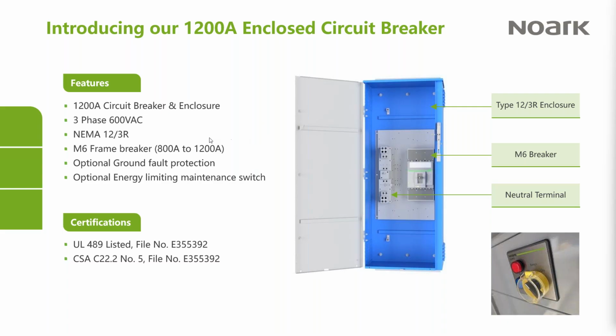So now talking about expanding the range, we also have coming very soon a 1200 amp enclosed circuit breaker. It comes in a type 12 3R enclosure. It uses our M6 breaker, has the neutral terminal just as you would expect. Because of the requirements of the code, we also will be offering ground fault protection and energy limiting maintenance switch with this offering. So more details to come. We'll make an announcement when we're ready to start taking orders for this.